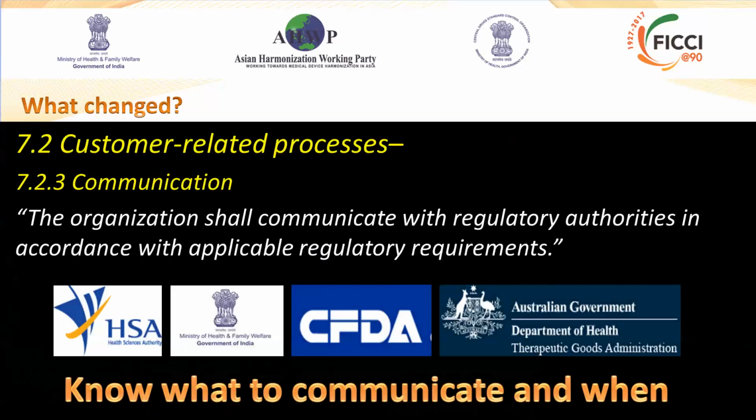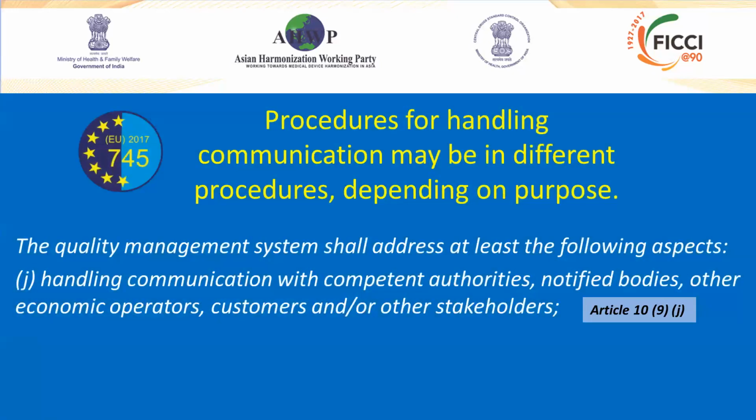Under the new EU regulation, there's going to be more requirements to keep what's called the EUDAMED database up to date as well. But the quality management system shall address the following aspects: handling communication with competent authorities, notified bodies, or other economic operators, customers, and other stakeholders. Those are statements within Article 10.9 of the new regulation.